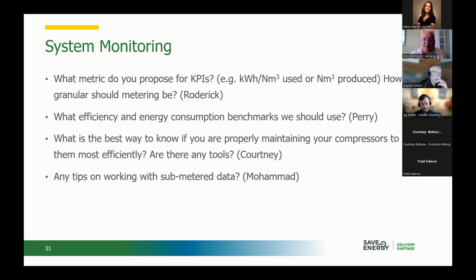Steve, did you want to take that one on kWh? I'll come back to the basic metering thing. It's one thing to calculate a metric - these are energy metrics, kilowatt hours per normal cubic meter of air, and kilowatts per CFM is a power metric. One is instantaneous and one is averaged over time. They'll tell you different things, but either way, you could be very efficient at generating air, but if that air isn't being used usefully or appropriately, or it's leaked, it doesn't matter how efficient the point of generation is.